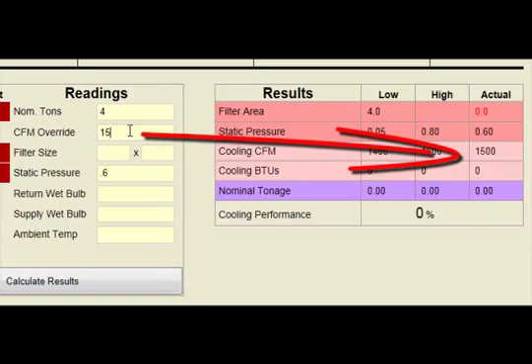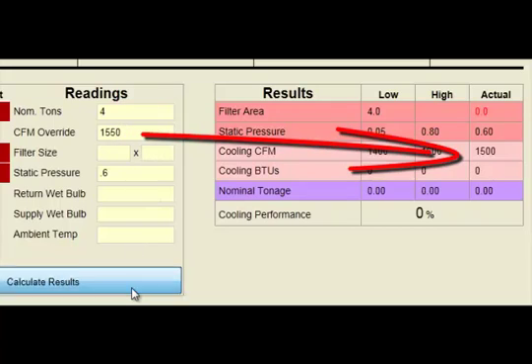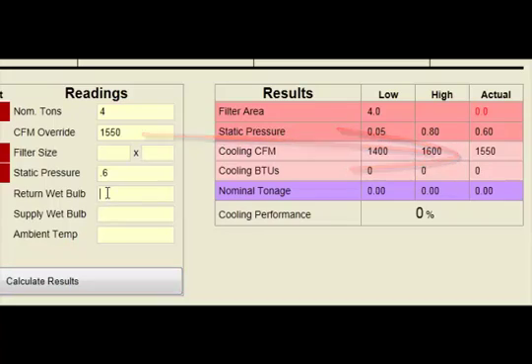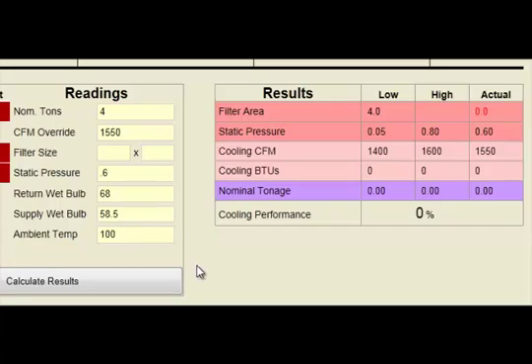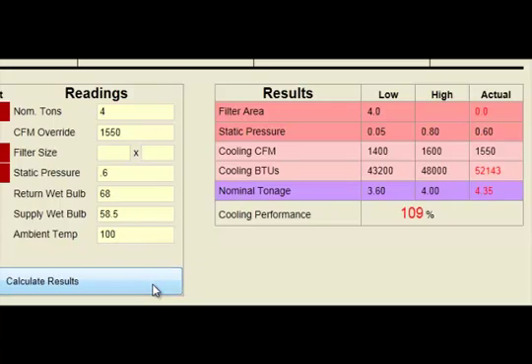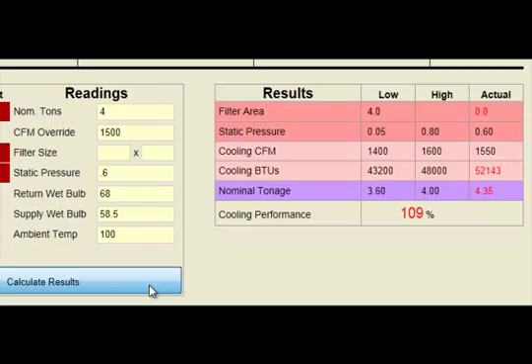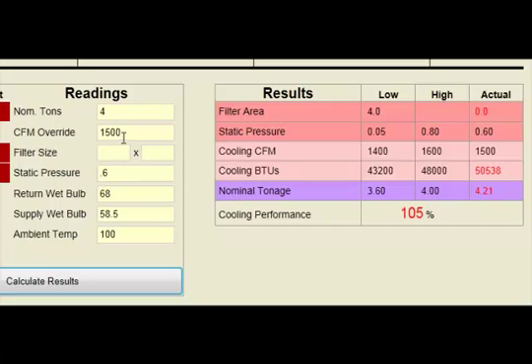To more accurately determine actual cooling CFM, use the cooling CFM calculation procedures available in Total Performance Diagnostics heating worksheets, or if the client is on a scheduled maintenance program, technicians can find the calculated cooling CFM by pulling up the client's Winter Client Report using Total Performance Diagnostics Report look-up tool.